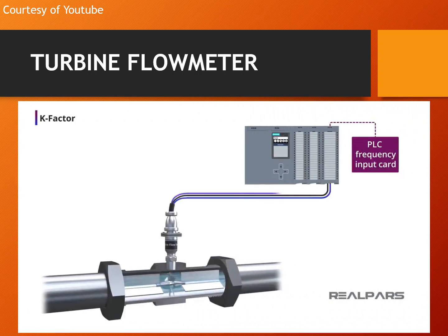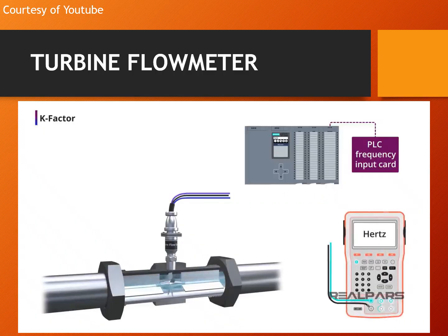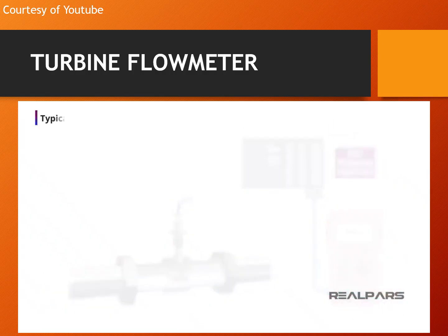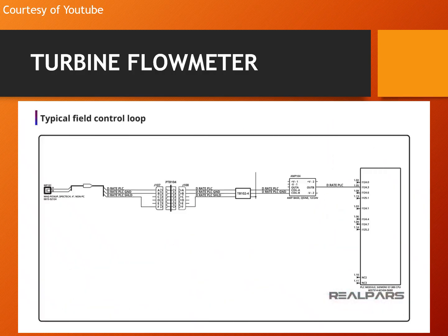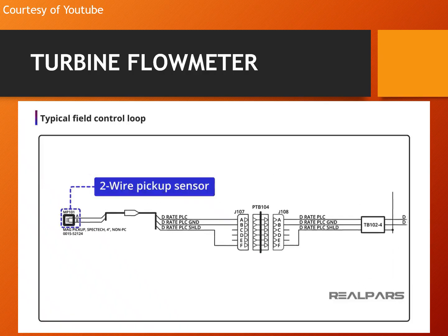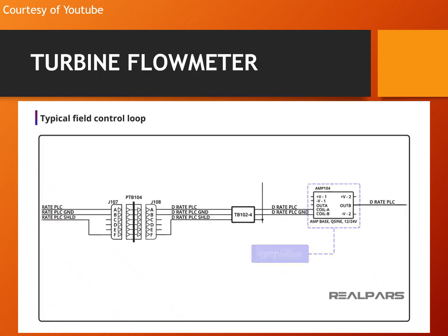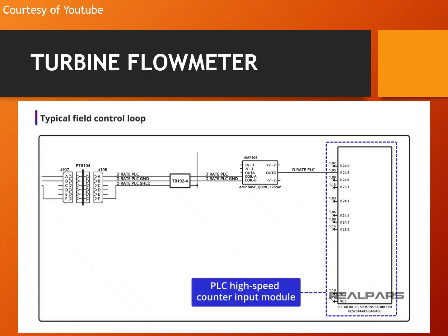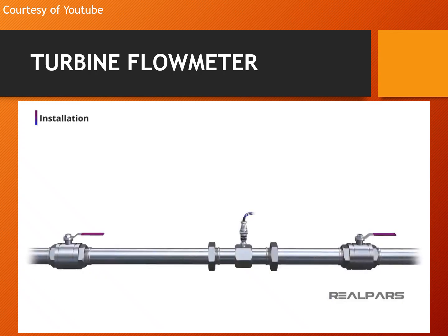We can connect the turbine flow meter to a PLC frequency input card. The input frequency now represents the volumetric flow rate. If we are troubleshooting or performing loop calibration, we can use a calibrator with a variable frequency output to simulate the turbine flow meter. Here's an example of a turbine volumetric flow rate measurement loop. A 2-wire passive sensor pickup unit produces AC-like pulses, which are conditioned by an amplifier, before being sent to a high-speed counter PLC input module. Typical installation requires 10 pipe diameters upstream of straight pipe and 5 pipe diameters downstream.